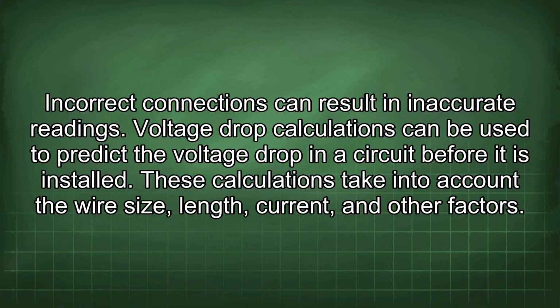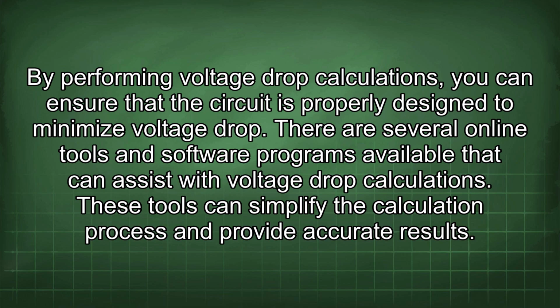Voltage drop calculations can be used to predict the voltage drop in a circuit before it is installed. These calculations take into account the wire size, length, current, and other factors. By performing voltage drop calculations, you can ensure that the circuit is properly designed to minimize voltage drop. There are several online tools and software programs available that can assist with voltage drop calculations. These tools can simplify the calculation process and provide accurate results.